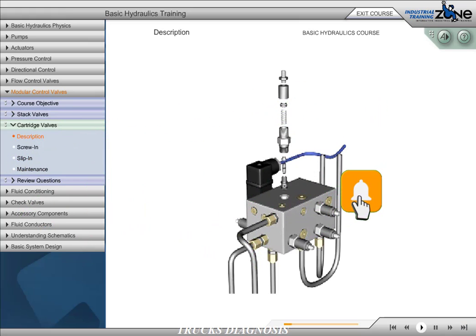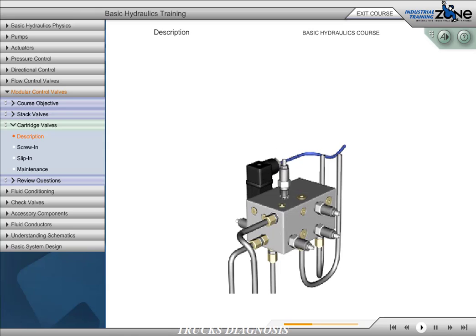Cartridge valves can be used to perform flow control, pressure control, directional control, load holding, and logic functions. They are a very compact design that must be installed into special cavities in valve blocks or manifolds. Cartridge valves, used in combination with a manifold, can be used to create a common circuit free of potential leaks associated with external plumbing. Cartridge valves can be divided into two design categories: screw-in and slip-in.